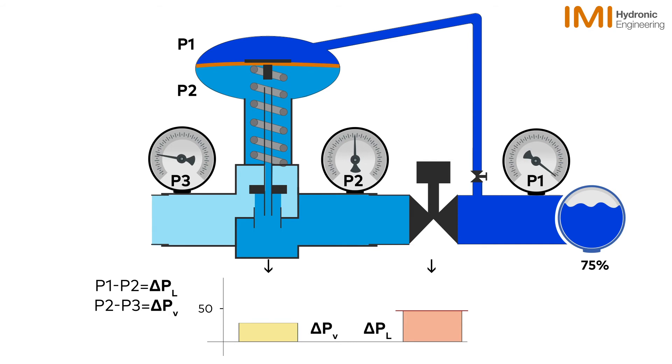The DPCV will constantly see a change in delta PL and act upon it as flow is reduced. It is able to accurately control delta PL until such a time as it reaches its minimum opening.